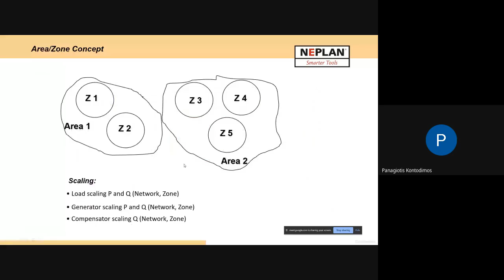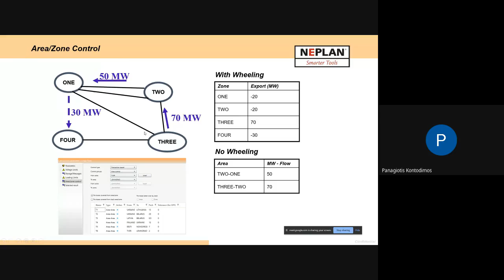Then we have area control, when we have, for example, cross-country contracts where we have a contract from one area to another. I don't know if in India there are also such transfers between states, but anyway, if we have the model of the network split into zones or areas, we can fix the load flow from a specific tie element at a certain power. Because if you run the load flow, this power will be dominated by the physical laws. But if there's a contract, if there's a controller, then we can fix the power between different zones or areas.